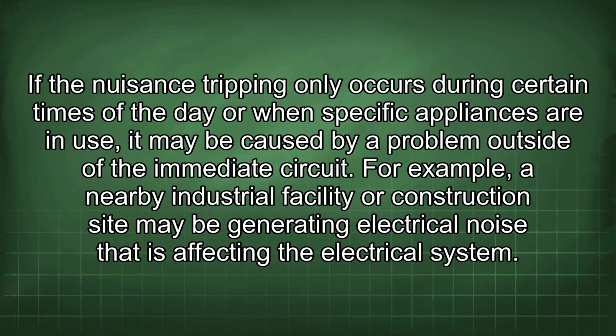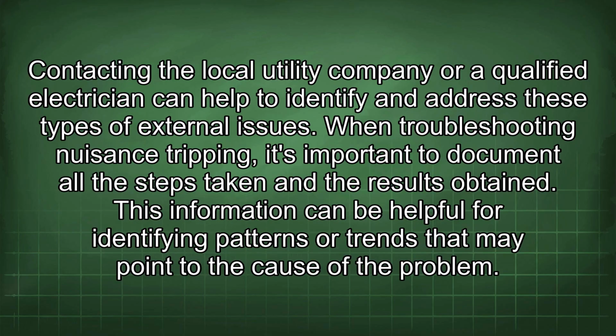If the nuisance tripping only occurs during certain times of the day or when specific appliances are in use, it may be caused by a problem outside of the immediate circuit. For example, a nearby industrial facility or construction site may be generating electrical noise that is affecting the electrical system. Contacting the local utility company or a qualified electrician can help to identify and address these types of external issues.